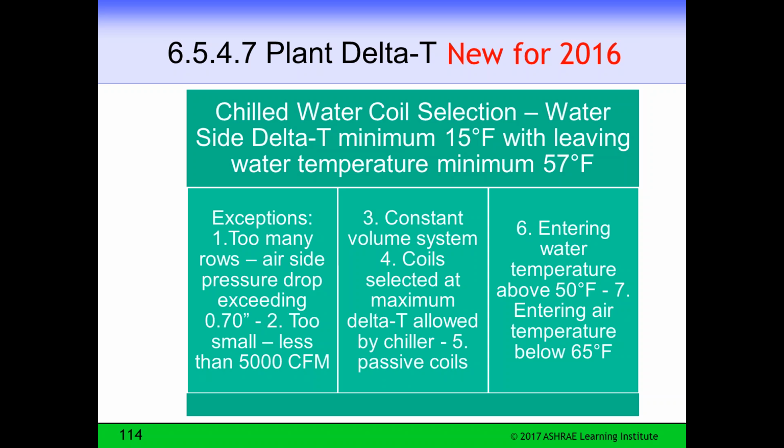Entering water temperature above 50 degrees. If you've got some kind of process where you're always using warmer water, and warmer water is going to save a lot of energy at the chiller, then we're not going to make you do it at the coil. Entering air temperature below 65, that would require you to use colder water coming in, and so you couldn't keep that minimum temperature.